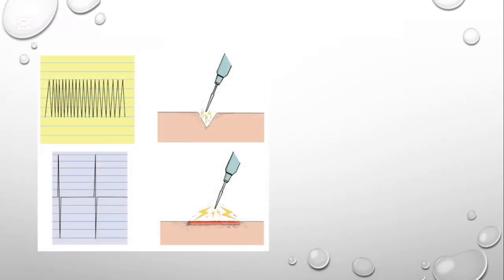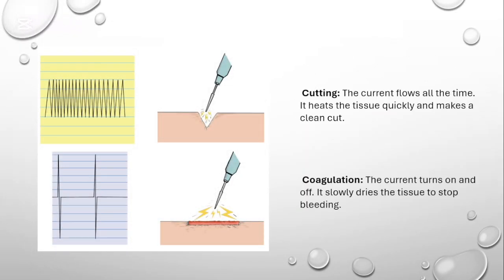Cutting mode. The electric current stays on all the time. It makes a lot of heat very quickly. This heat cuts the tissue by turning it into vapor. It helps make clean cuts and does not harm nearby areas too much. Coagulation mode. The current turns on and off in short bursts. It makes less heat more slowly. The heat dries the tissue and helps stop bleeding by making the blood clot.